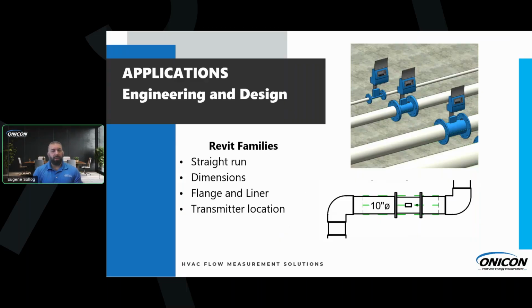Another relatively new feature, thanks to one of our talented mechanical engineers here. He has designed these extensive Revit families that, when used, take all the guesswork out of any new engineering design drawing. Basically, you just take the Revit family and it'll outline the straight run for you. As you can see in that picture, the green dotted line is the actual straight run needed for a 10-inch pipe.